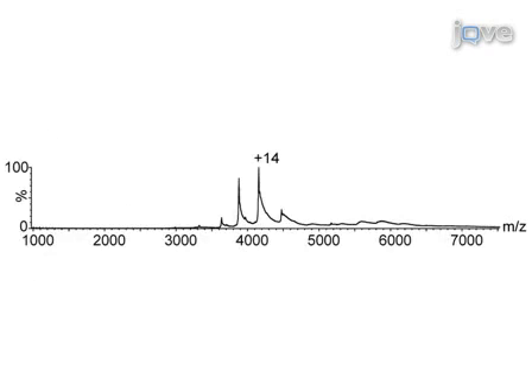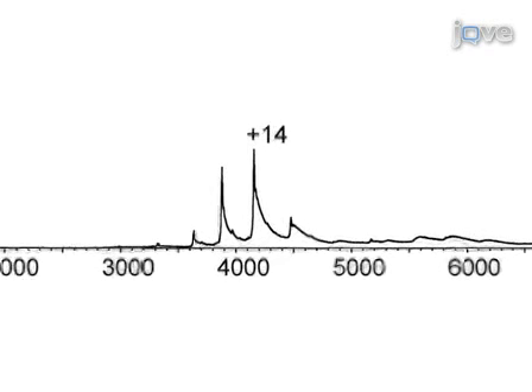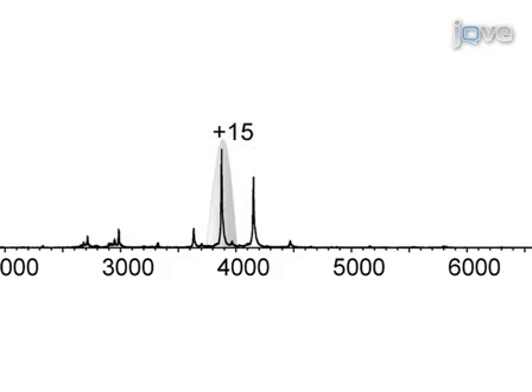Here is an example of mass spectrometry of a lectin variant complex, giving rise to a charge state distribution between 3000 and 5000 mass-to-charge ratio. However, due to inadequate desolvation of the ions, the peaks are broad. Increasing the bias voltage from 4 volts to 15 volts, which brings about an increase in accelerating conditions, causes the stripping of residual water and buffer components, yielding a highly resolved spectrum. The measured mass corresponds to a pentameric complex.